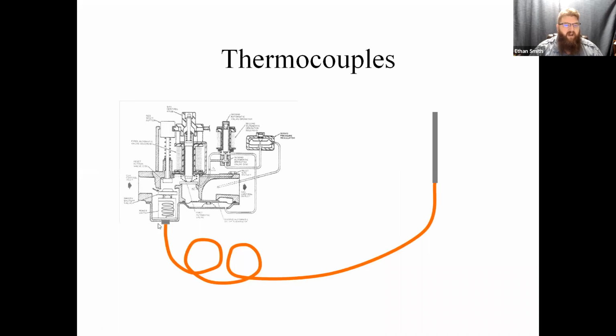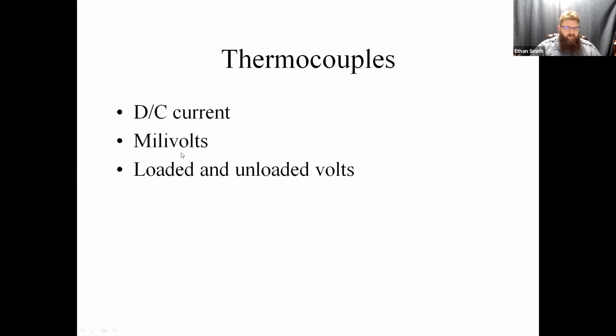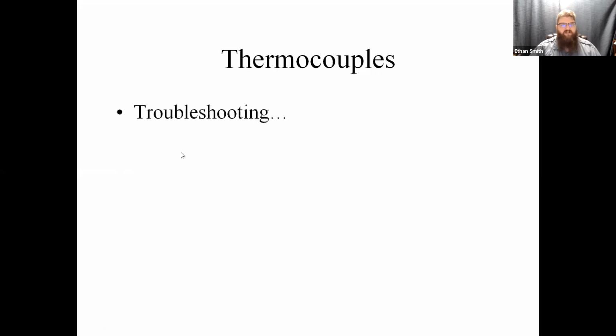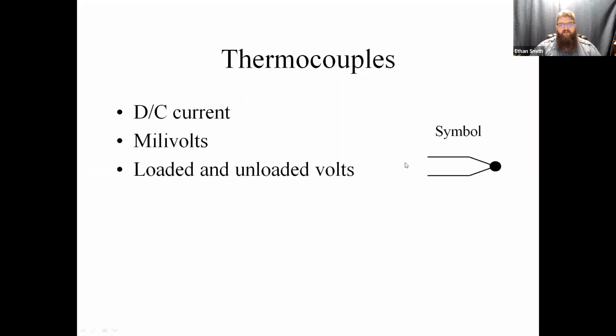That little pilot solenoid is a very, very small solenoid that allows just enough gas through to keep the pilot light lit. If you need something that generates a little more power, we can go to a little different device that we'll talk about in a second. The thing to remember is thermocouples are just little DC voltage generators measured in the millivolts, typically around 37 millivolts, I believe, if my memory serves properly. There's the electrical symbol for a thermocouple.